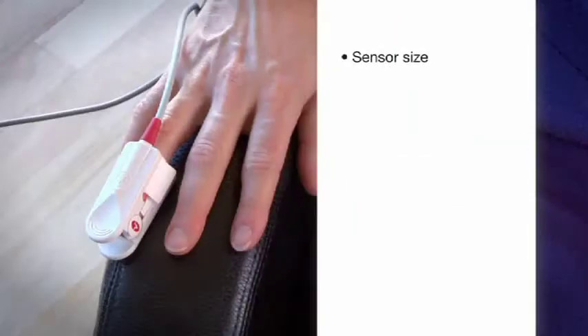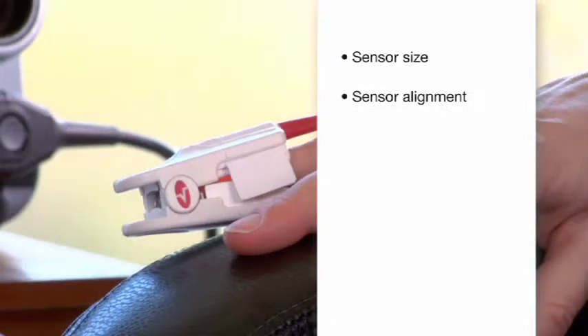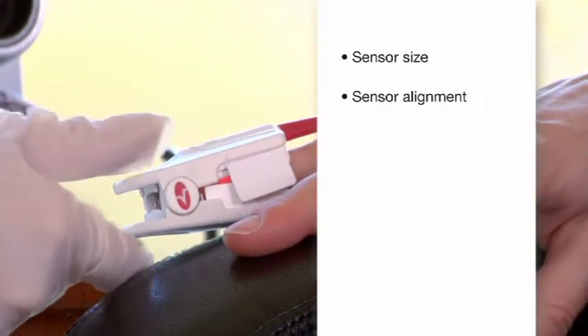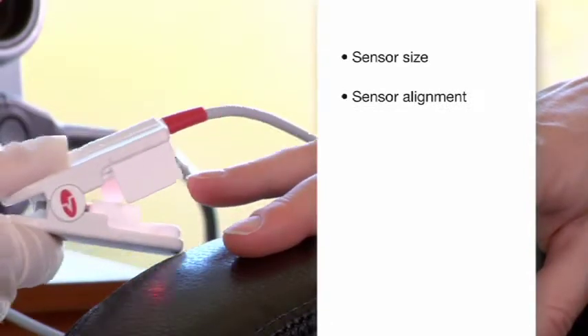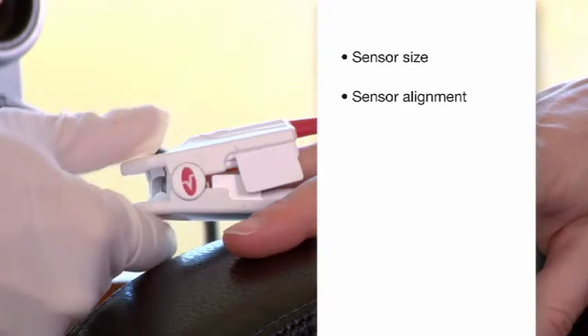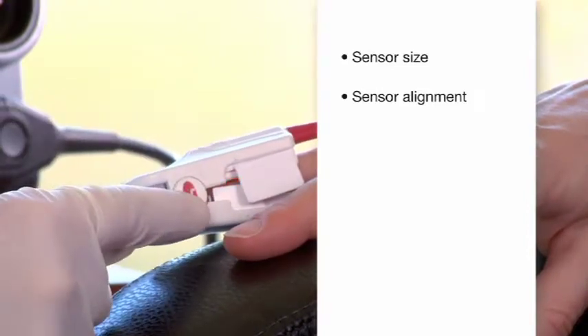If you have difficulty getting a stable signal or the value shown is questionable, consider these factors. Is the sensor size correct for the patient? Consider using a pediatric sensor for adults with small fingers. Is the sensor aligned properly on the patient's finger? Try taking it off and putting it back on again. Make sure the tip of the finger touches the raised stop inside the sensor.